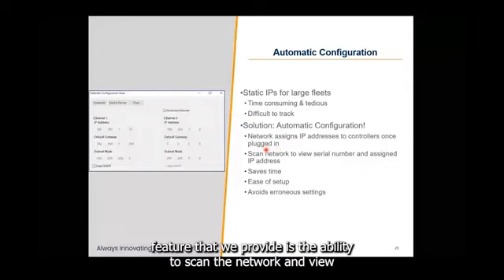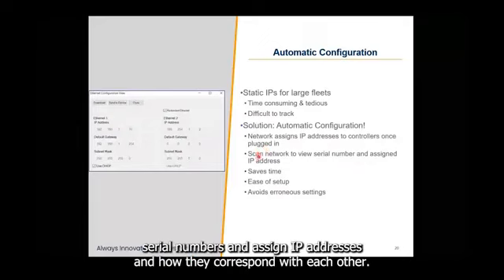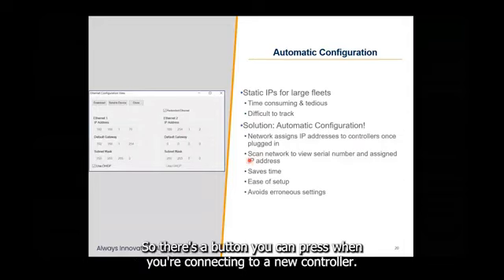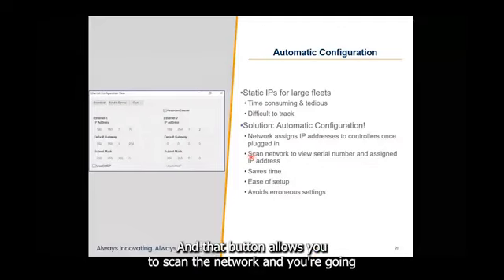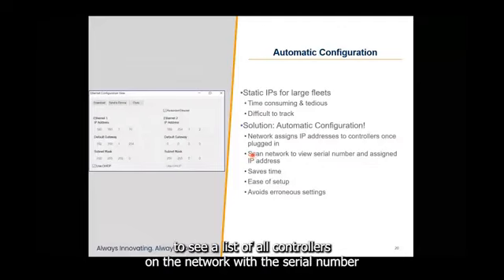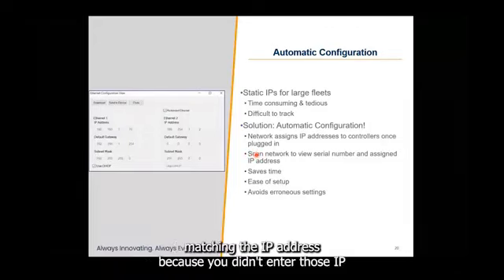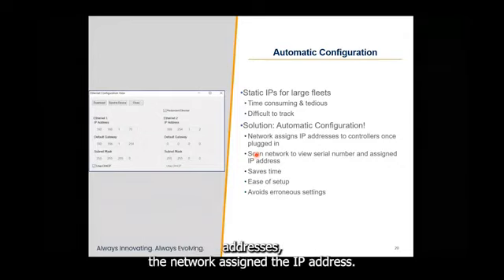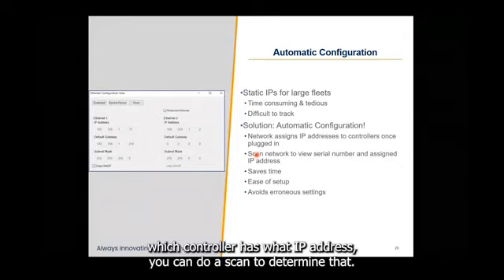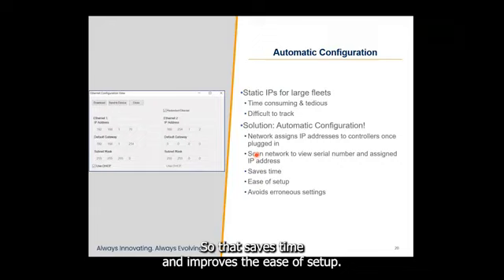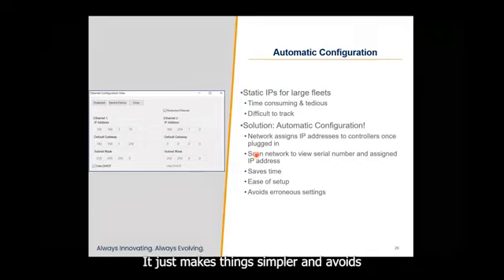Another really neat feature that we provide is the ability to scan the network and view serial numbers and assigned IP addresses and how they correspond with each other. There's a button you can press when you're connecting to a new controller, once you're establishing a new connection. That button allows you to scan the network, and you're going to see a list of all controllers on the network with the serial number matching the IP address. Because you didn't enter those IP addresses, the network assigned them. So if you want to know which controller has what IP address, you can do a scan to determine that. That saves time, improves the ease of setup, makes things simpler, and avoids potential erroneous settings.